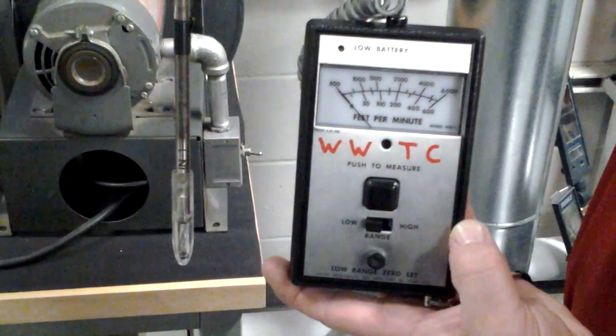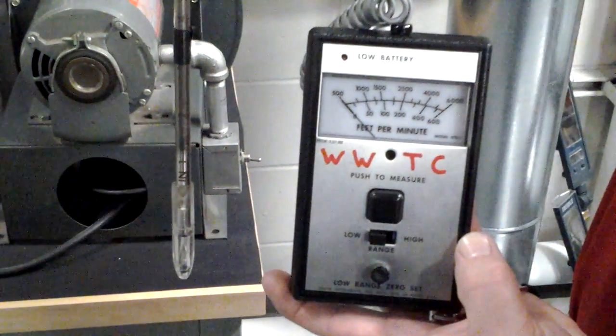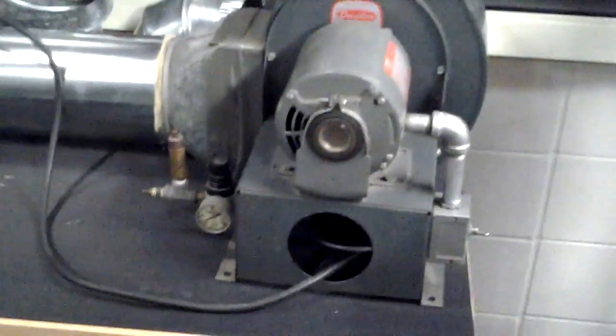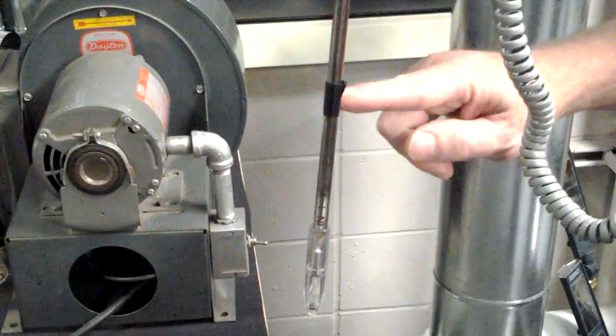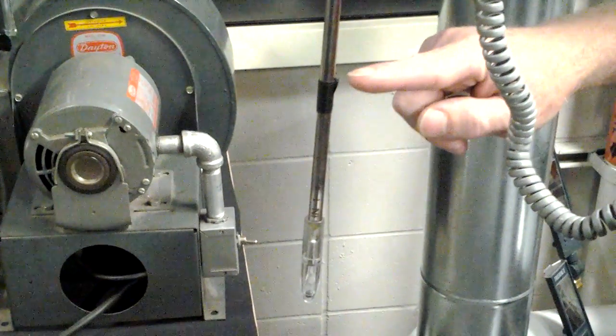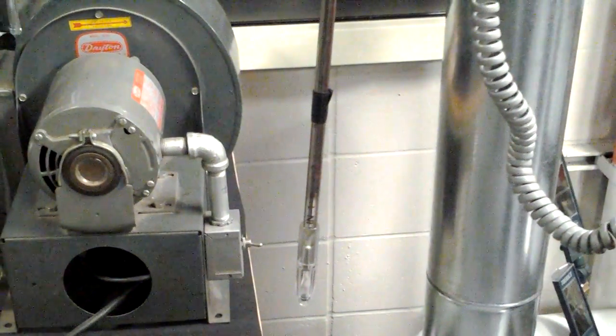We will be demonstrating how to use this by using a direct drive blower and 15 feet of 6 inch round duct to simulate a branch in your residence. Let's begin by putting a piece of electrical tape at the 3 inch mark on the anemometer probe, because it will center the probe in the duct.